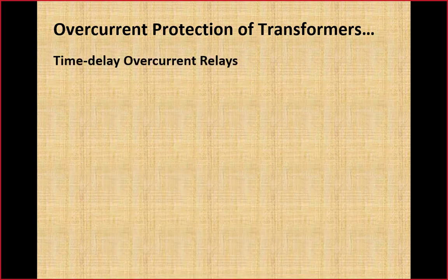Now this was the protection of transformers mounted on poles, known as pole mounted distribution transformers, and these transformers are protected with the help of fuses. We have seen that the purpose of those fuses is just to detect a short circuit fault on the transformer HT side, but those fuses cannot provide protection against overload conditions.